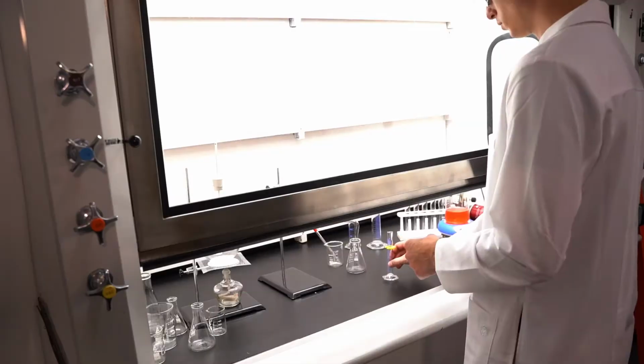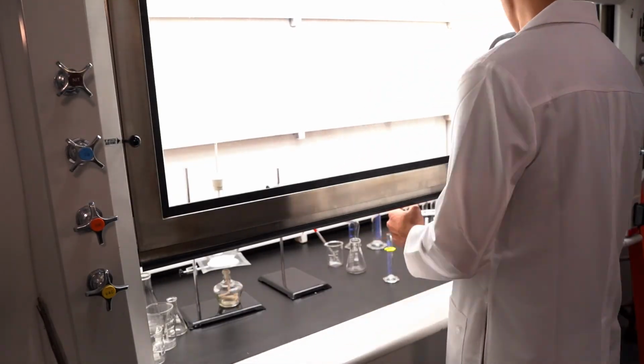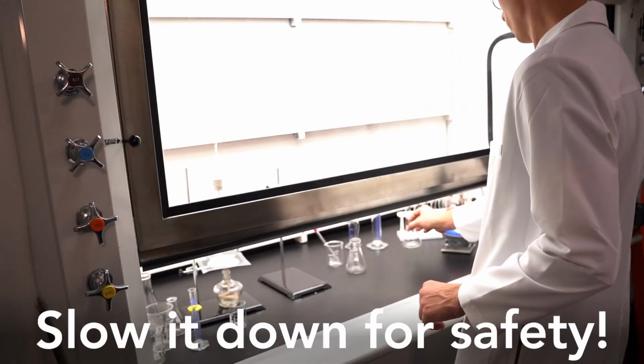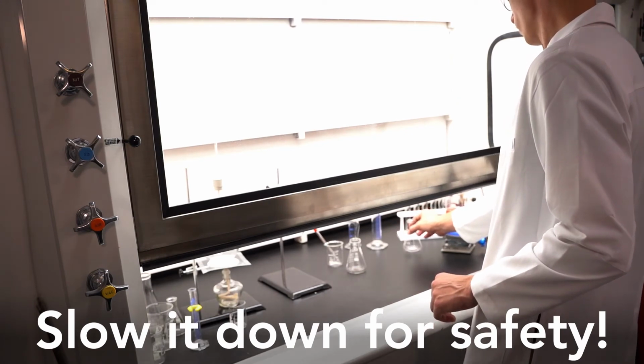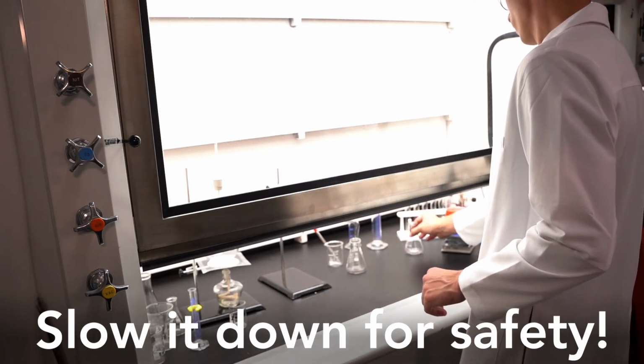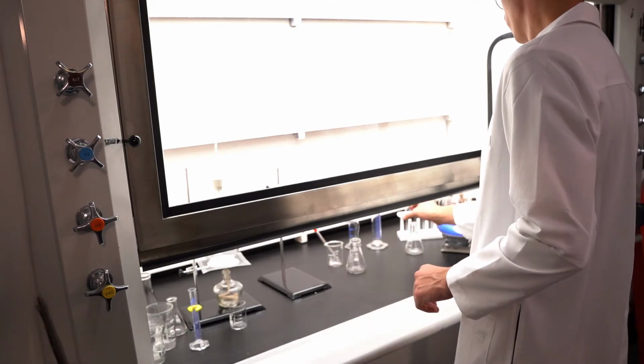A component of turbulence is velocity. The faster we move in and around the hood, the more turbulence we create. The faster we open and close the sash, the more turbulence we create. When working with a fume hood, slow and deliberate movements are best. At the end of the day, there's only one way to know that your fume hood is performing, and that's to have it tested as you're using it.